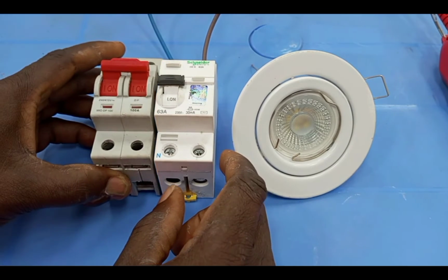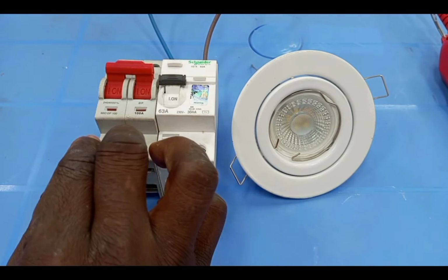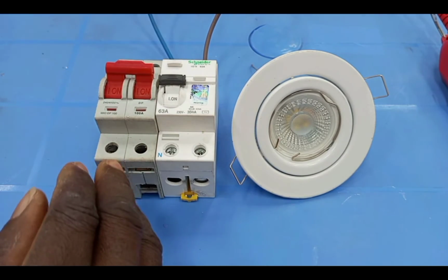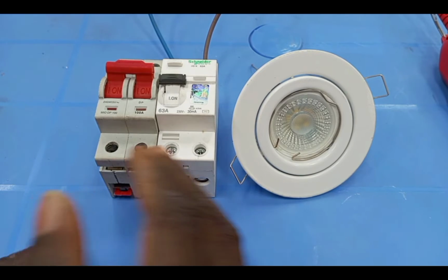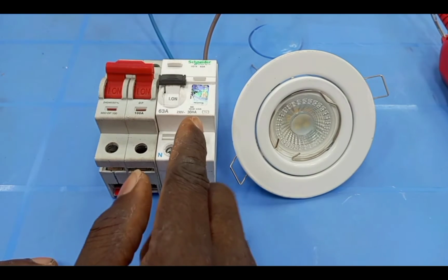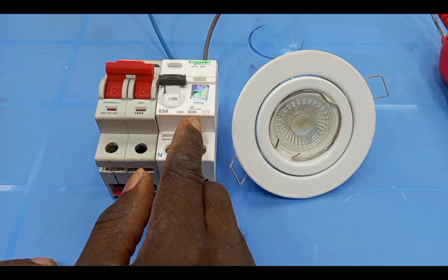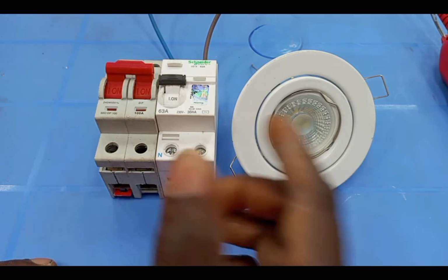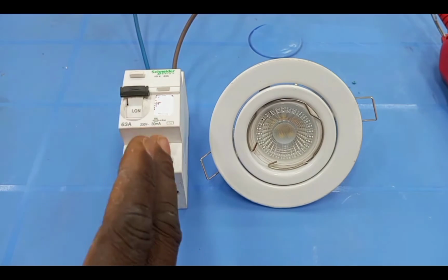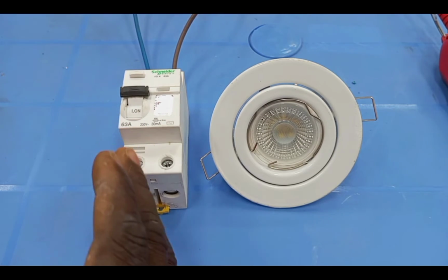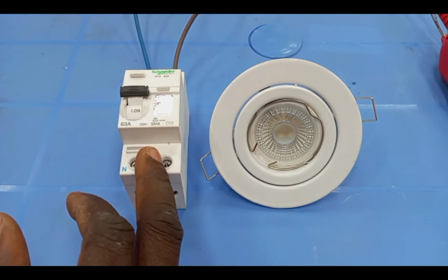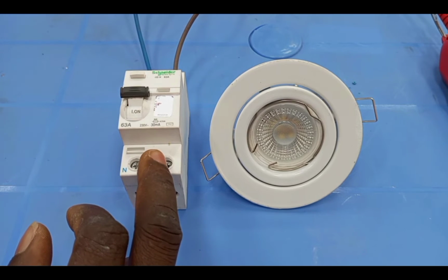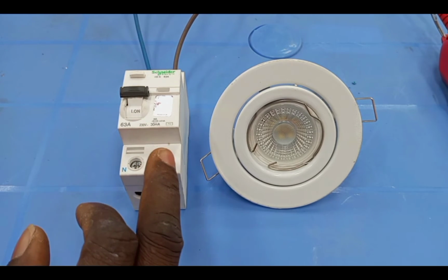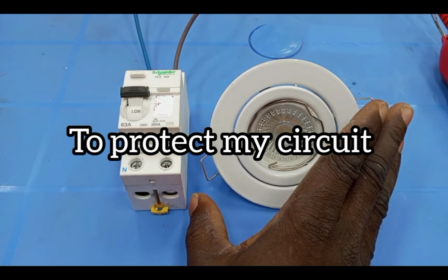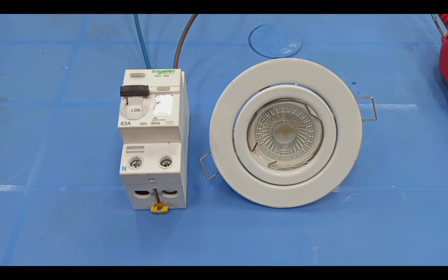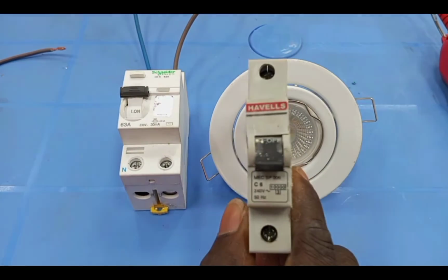You have to use the MCB. So the MCB will be protecting against overload and short circuit, and then the RCCB will be protecting against leakage. Because this is an RCCB and it doesn't offer protection against overload or short circuit, I have to use a miniature circuit breaker together with this one to protect my circuit. Okay, so then a miniature circuit breaker has to come in.